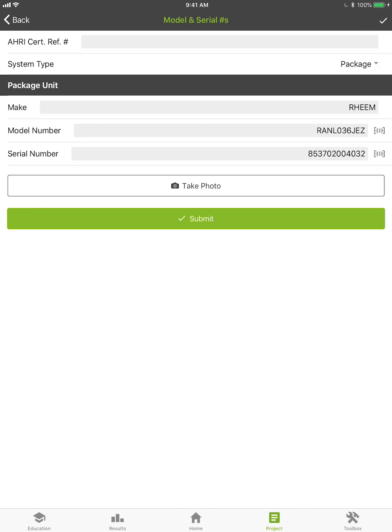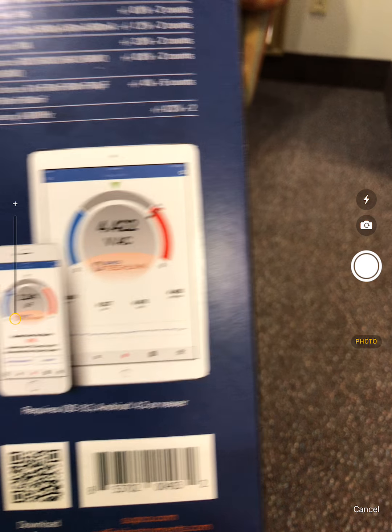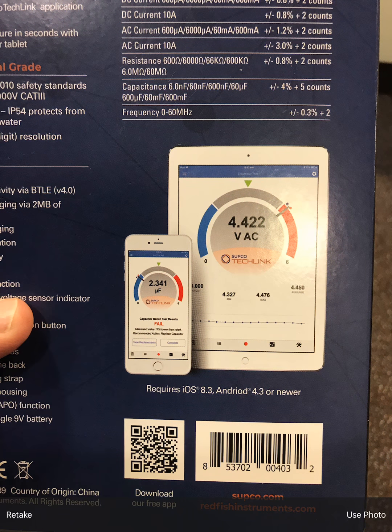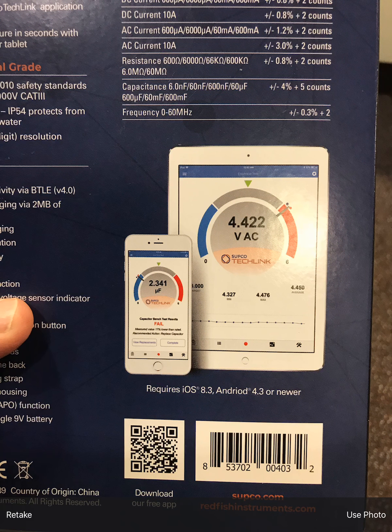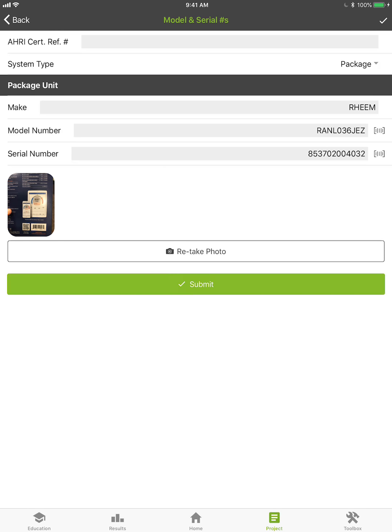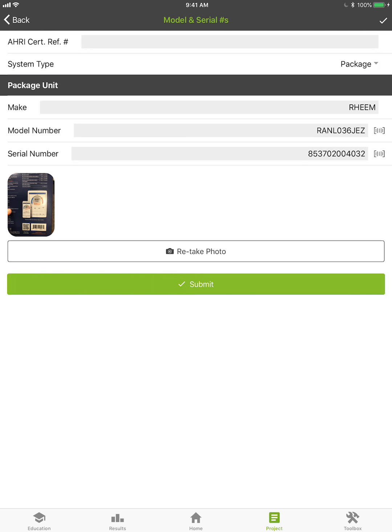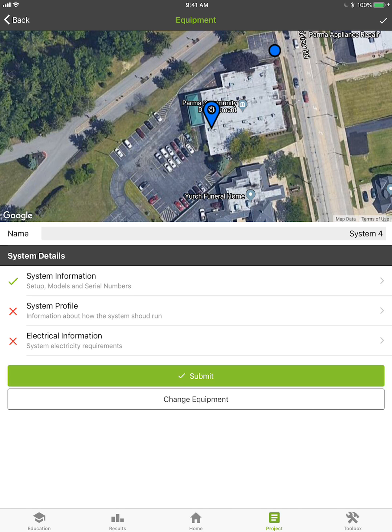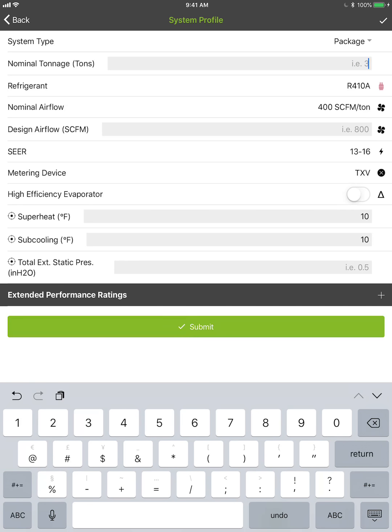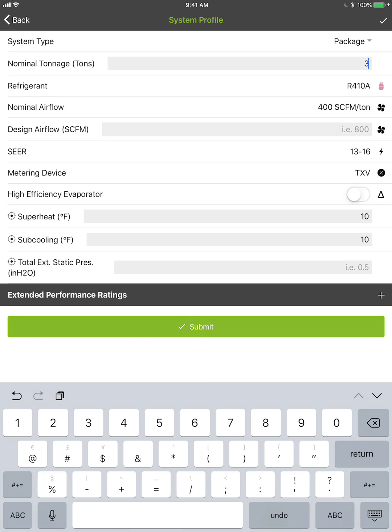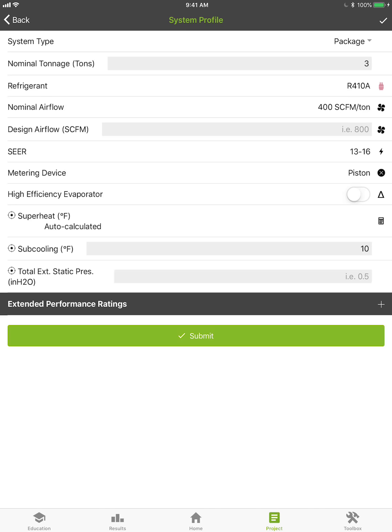You can also take a photo of the label — hit the photo button, center what you want, click it, and it automatically stores the photo. Tap 'Use Photo' and that photo goes into the project. If there are any corrections to model or serial numbers later, we have that information right at our fingertips. Hit Submit and that check mark goes green. For the profile, I'll say it's a 3-ton unit, R-410A, 400 CFM per ton, piston metering device. The superheat is auto-calculated and subcooling defaults to 10.